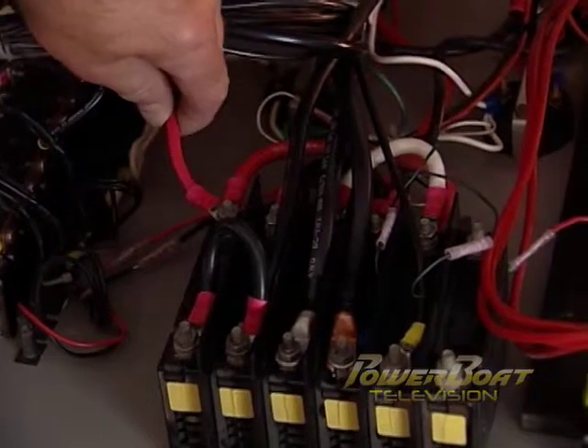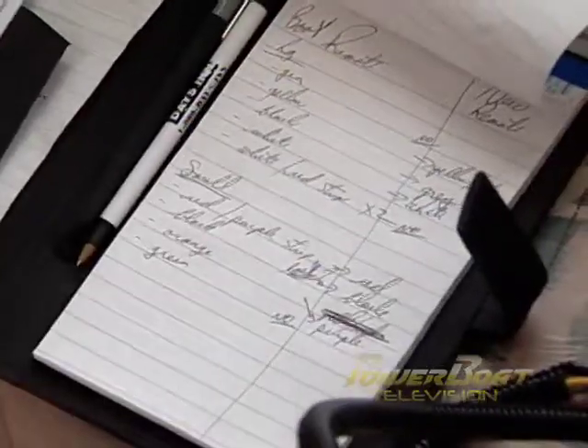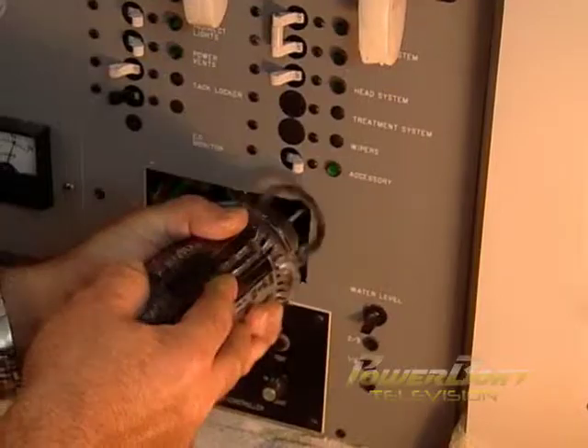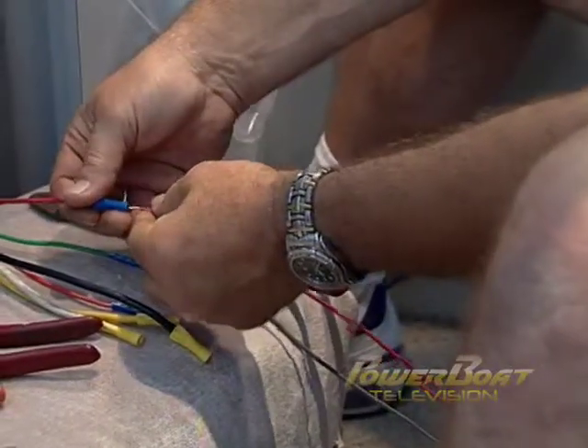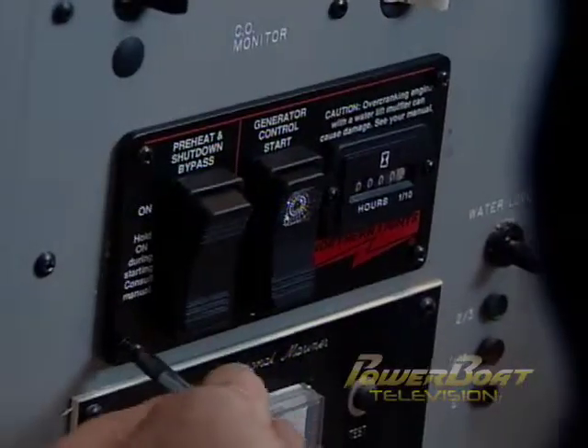While Sean and John continued below, Steve started work on the electrical and control hookups, first inspecting all AC supply wiring to ensure it was up to code and that the load on the panel was properly balanced. The plan was to use the existing control cable and tie the new control in by first mapping out the color scheme of the wiring. Using a zip saw, an opening was expanded in the panel and the wiring fed through to ease the connection process. Following the color code notes, Steve stripped the wire, crimped on the connectors, staggering the connections to reduce the bundle diameter. Finally, heat shrink tubing was applied to tidy up the harness, then the control was mounted in the panel.